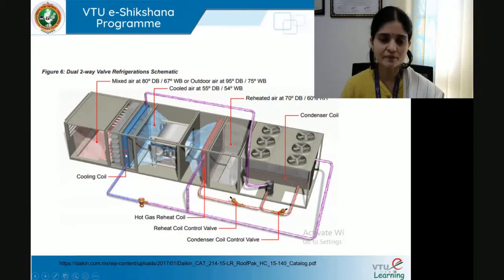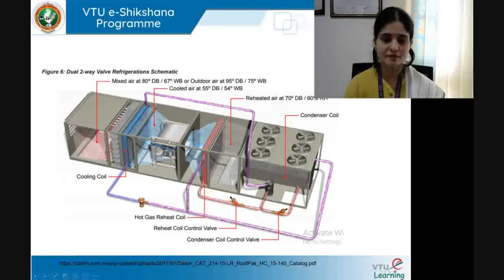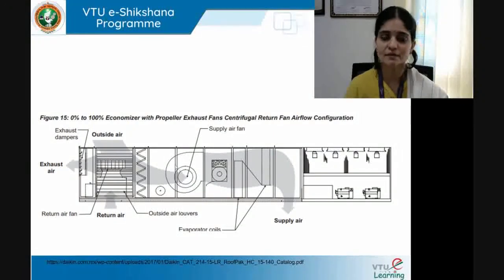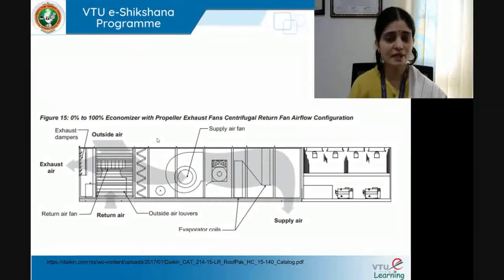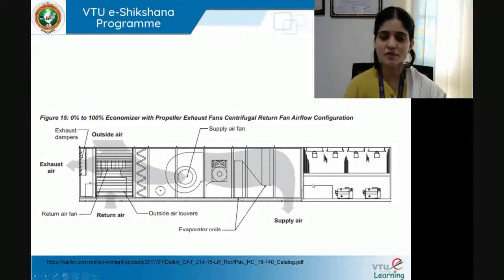Looking at the cooling coil on the left, the filter is positioned just before it — air passes through the screens, gets cleaned, and enters the coil. The red mixed air turns to cold air. A sectional elevation can be drawn and labeled with the parts: exhaust dampers, exhausted air, influx of outside air, return air, and outside air mixing in the chamber, then passing through louvers and evaporative coils, with supply air coming back out.